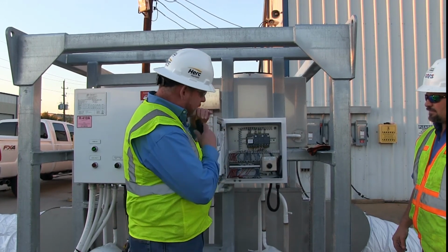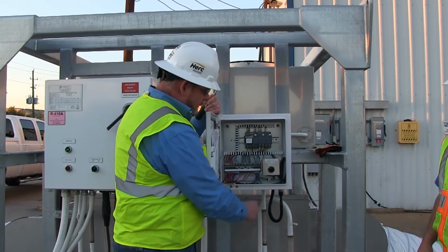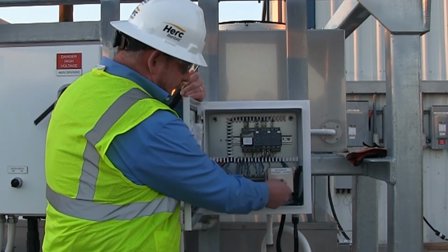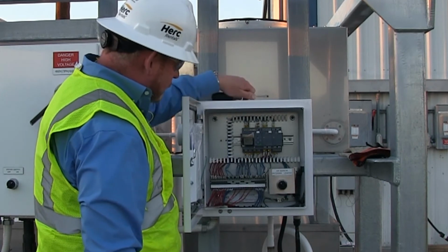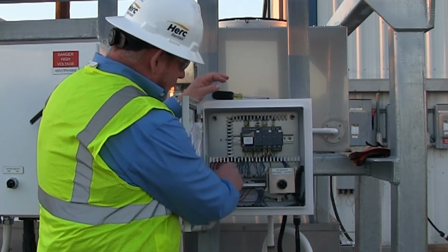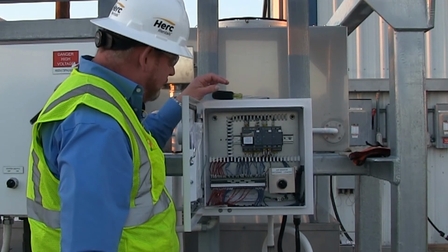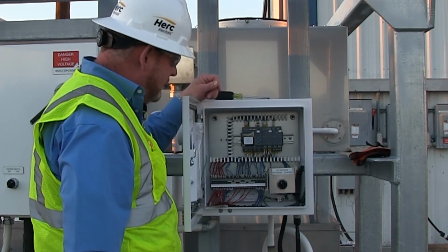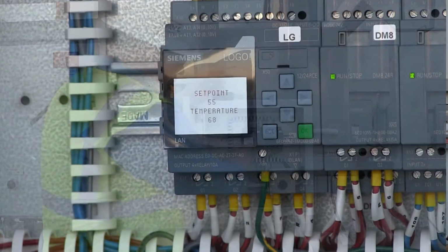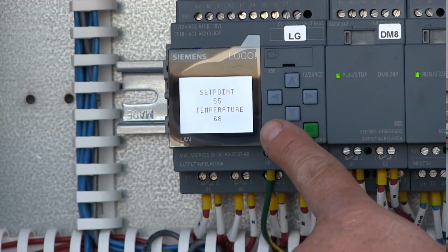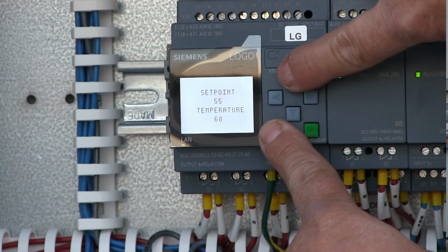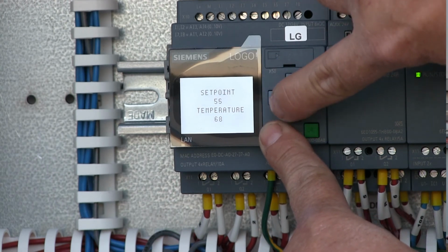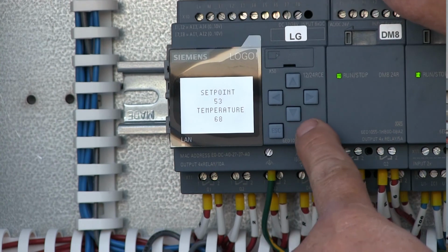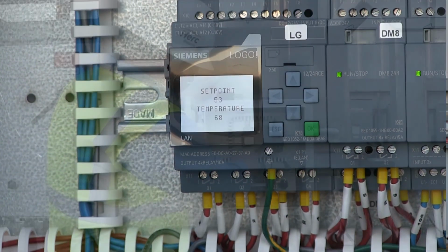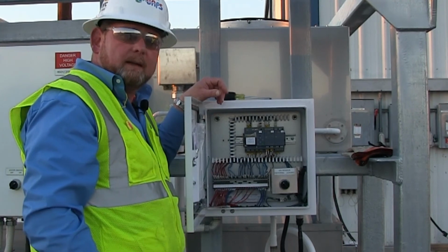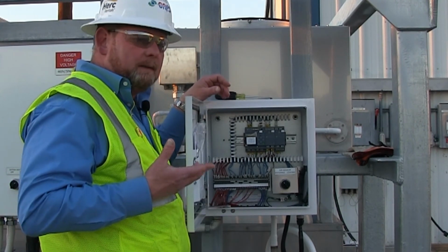First thing you need to do is make a decision if you want to control the unit on the entering airstream or the leaving airstream. In this case, it's set for entering air. The controller is booted up. Its current set point is 55 degrees. The current temperature outside is 68. To make a change on temperature, you simply hold the escape key down and raise the arrow up to 56, 57, or down to 54. After you've set it where you like it, push the OK button, which is the green, and now you've set the thermostat.